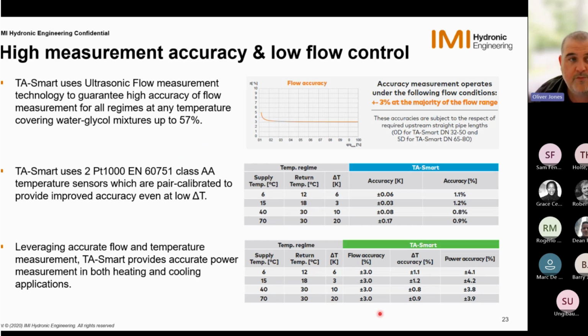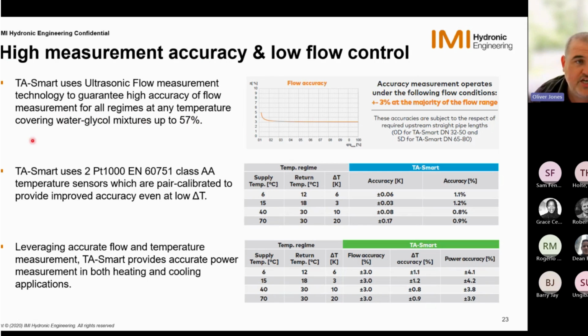So flow measurement, as I said, we use an ultrasonic flow measurement device, and this gives us a high accuracy of flow. We can also use it for all regimes at any temperature, so we're not just restricted to an accuracy at certain specific temperatures like some others are. And we can also cover glycol mixtures up to 57%. So as you can see from this table here, we're actually at 3% at the majority of the flow range, and it just tails off towards the end and goes to a 5% accuracy, which is not bad at all.